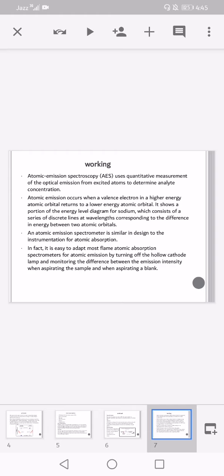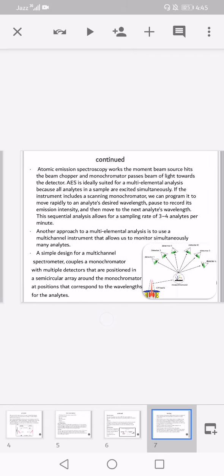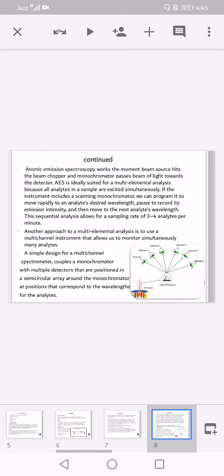An atomic emission spectrometer is similar in design to atomic absorption instrumentation. In fact, it is easy to adapt most flame atomic absorption spectrometers for atomic emission by turning off the hollow cathode lamp and monitoring the difference between the emission intensity when aspirating the sample and when aspirating a blank.